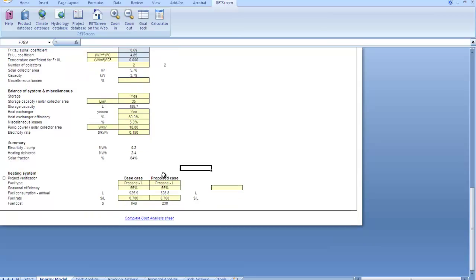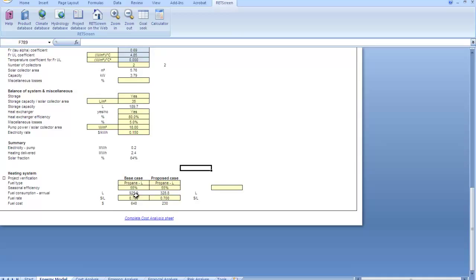So between base case and proposed case, RETScreen will always put the renewable energy system automatically into proposed case. You don't have to tell it to put it in proposed case. It just assumes that you're modeling renewable energy as a proposed case. So in this situation here you can see that we have fuel consumption is less in the proposed case than it is in the base case. And fuel cost is also less in the proposed case than the base case, all in this ratio of 64% because our solar is providing 64% of our water heating over the course of a year.